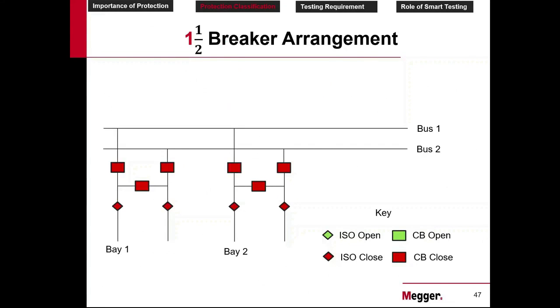1.5 breaker arrangement. So let's understand what the system is. You have the same 2-bus arrangement, but the drawing is like this. You have 3 breakers connected like this, 2 isolators. So like this, it keeps on going, bay 2, bay 3, bay 4, etc. So bay 1 is connected like this. It is supplying both the bus bars. It comes here and goes out. So this can be bay 3, this can be bay 4, etc. I have not written here because in our example we are discussing only 2 bays.